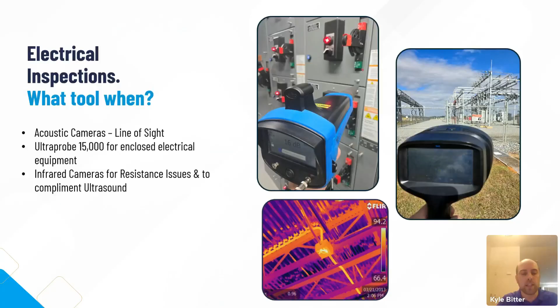But utilizing the camera on enclosures is not the best ultrasonic procedure - we'd want to use an Ultra Probe to safely open up the cabinet. From there, you can utilize the camera, scan your areas, and generate reports. You can also take it a step further, bringing in our partners from FLIR for infrared cameras to check for resistance issues. Ultrasound and infrared are technologies that work very well together, and we'd highly recommend pairing them up for a more thorough predictive maintenance program, especially for scanning electrical assets.